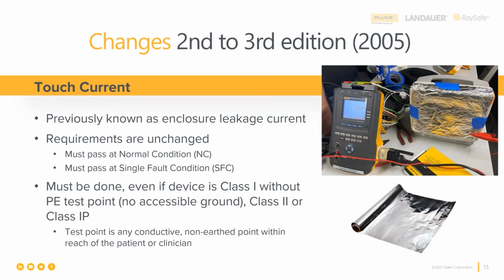Your test point is not the accessible ground pin on the medical device. It is a conductive connection that is not grounded. A conductive test point that is not grounded. Well, that's fine, except almost all of the newer medical devices are completely plastic. There is no conductive test point aside from the protective earth test point on the back or on the device.